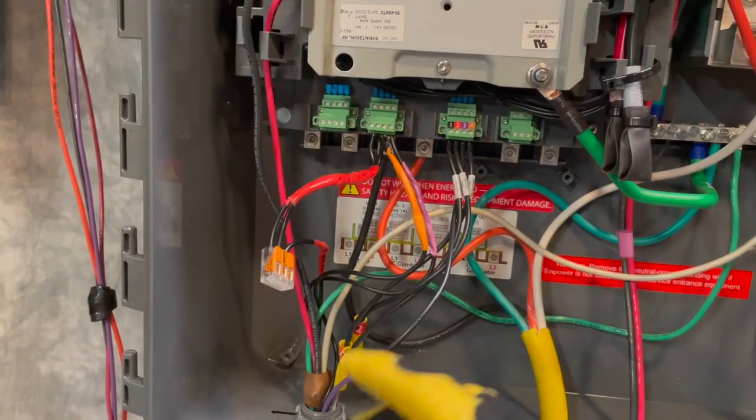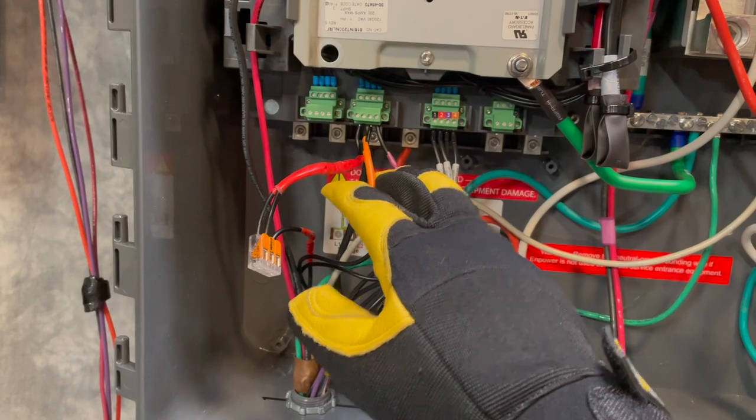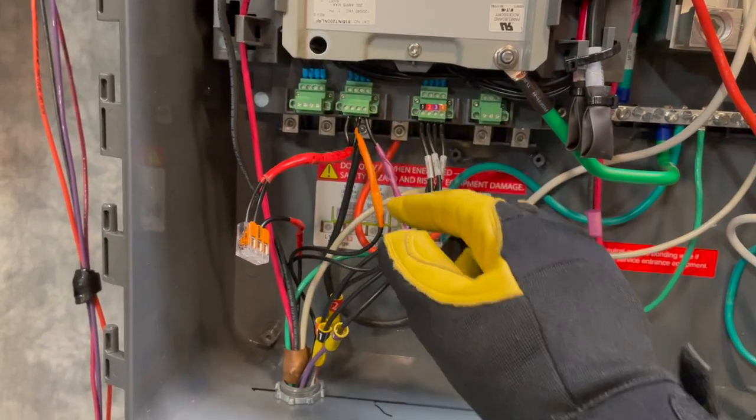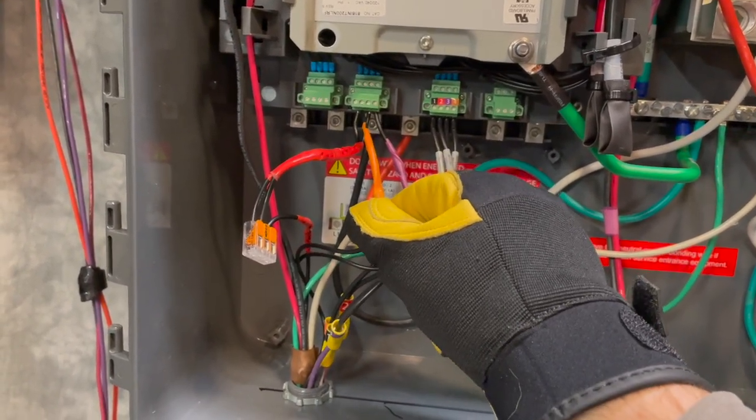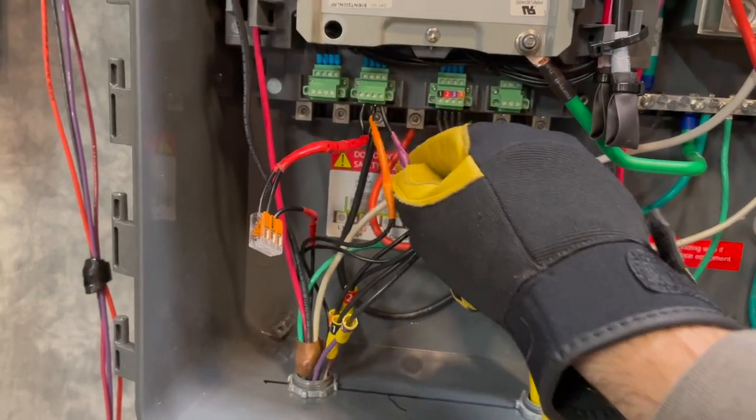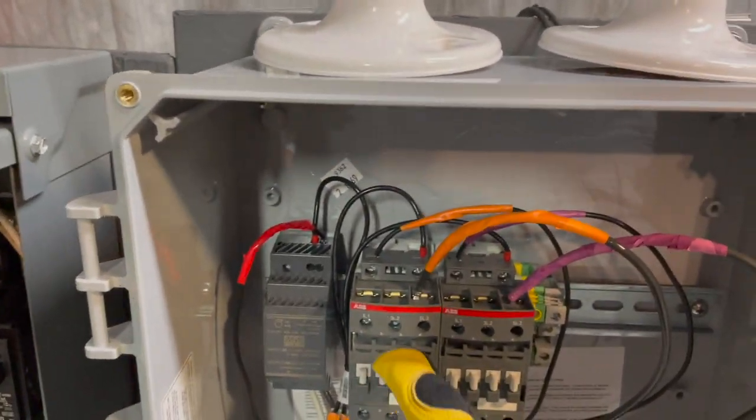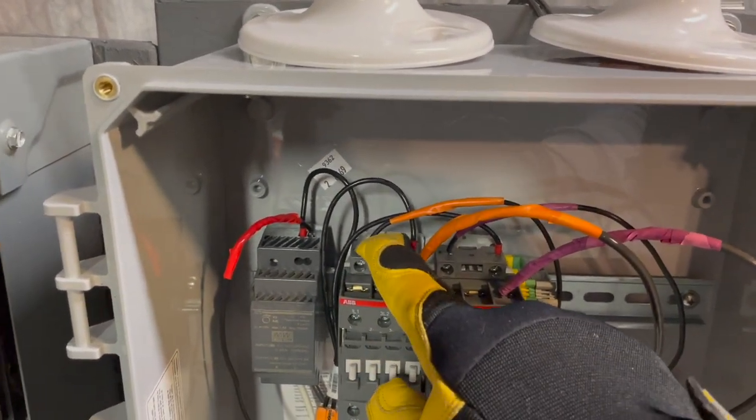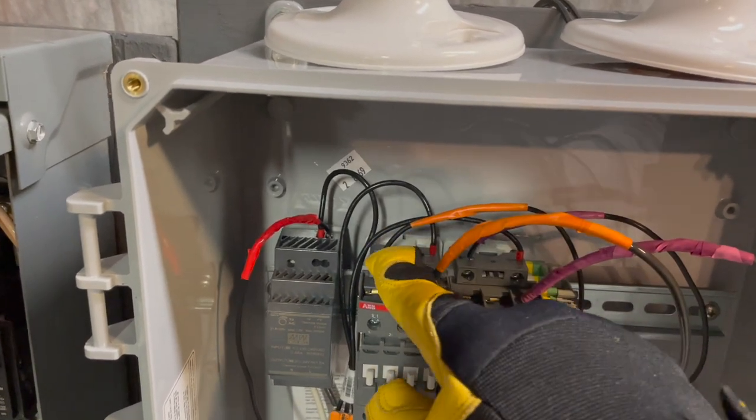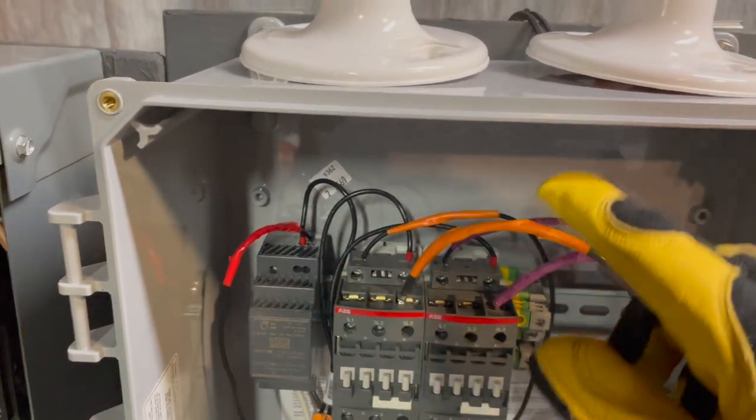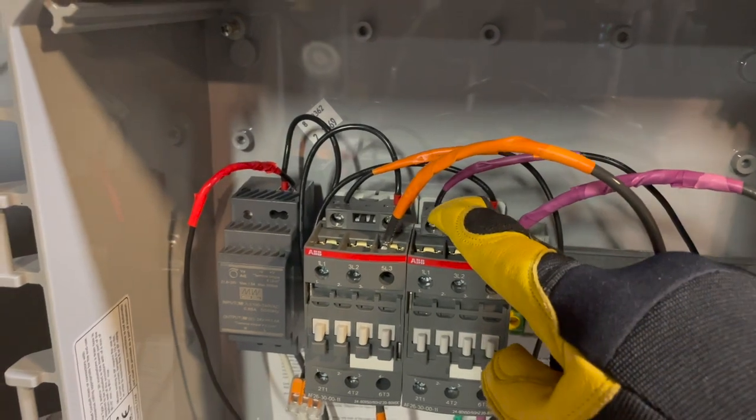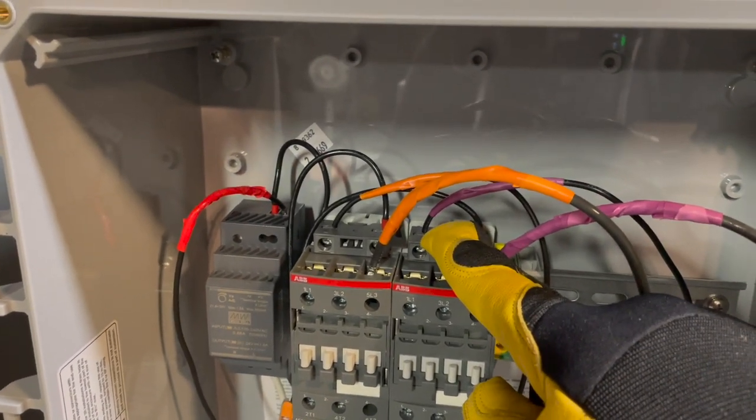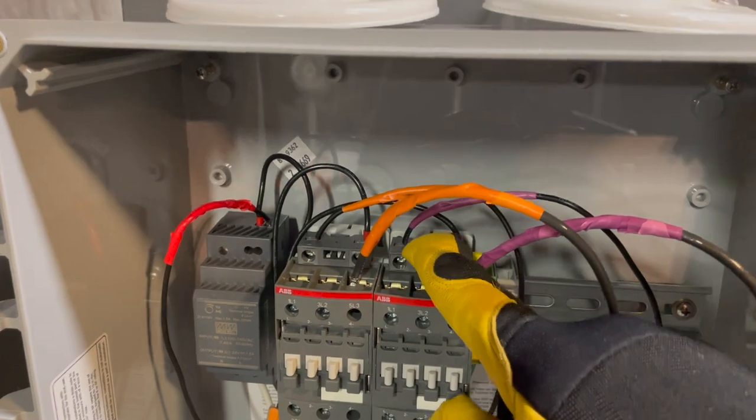Now it's important that you have separate return wires for each of those contactors. This one's going to be my NC1 out. Here's NC2 out and those return back here on each of the contactors. So there's my NC1 positive wire coming back to this contactor and here's NC2 control circuit, that 24 volt circuit returning as well.